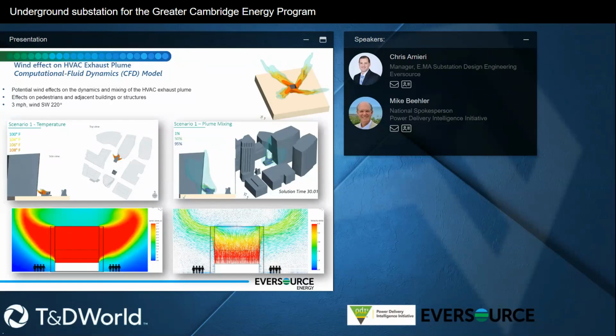But the air dilution, the plume mixing, that one does get a bit messier. It starts to expand. The good news, through the ventilation and other things we utilized, is that it's less than 1% air mixing when you get up to the topmost level of the commercial building. A person couldn't even distinguish between normal ambient air and one less than one percent.